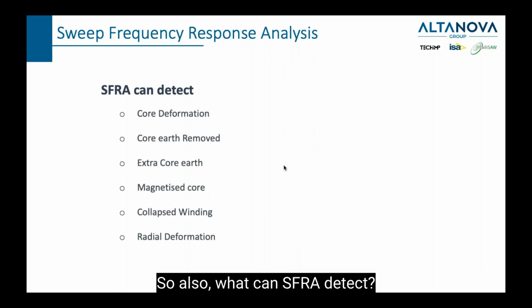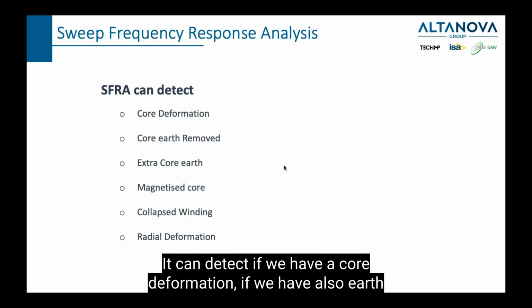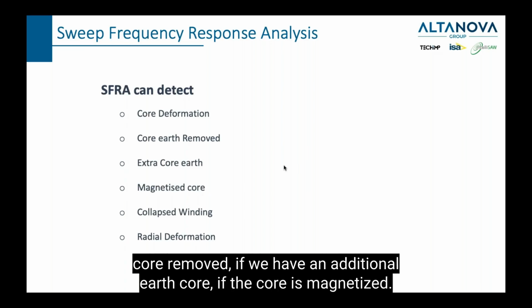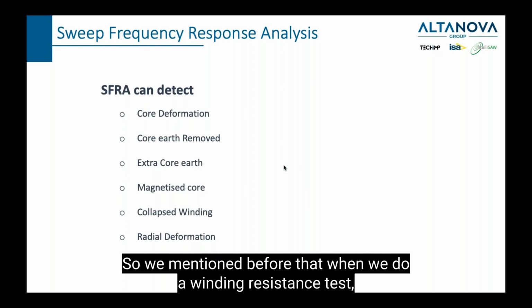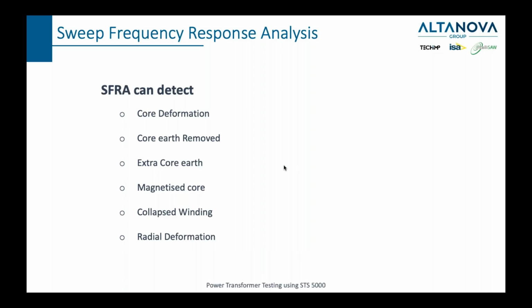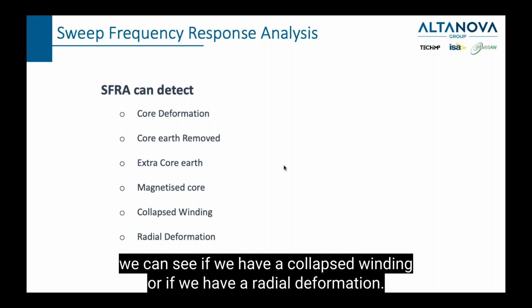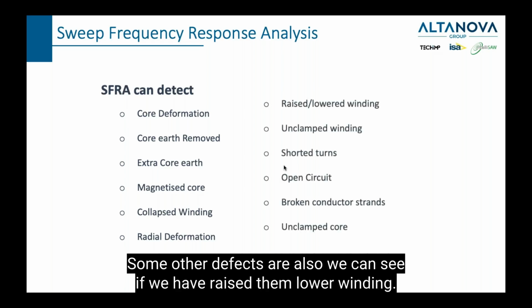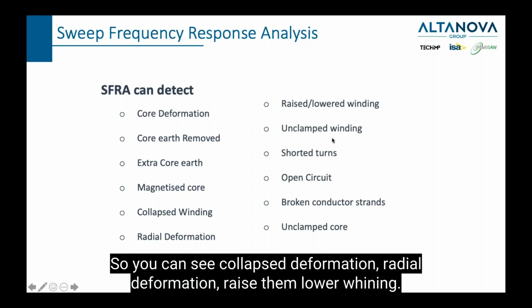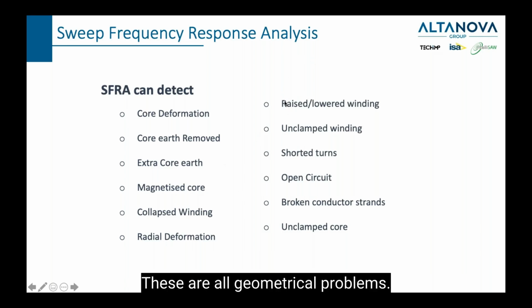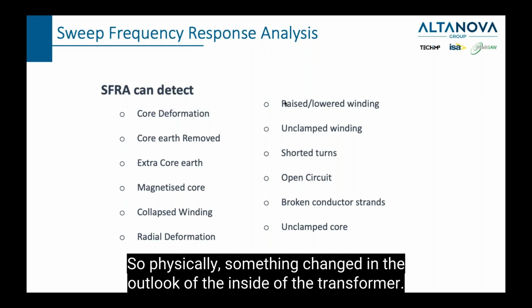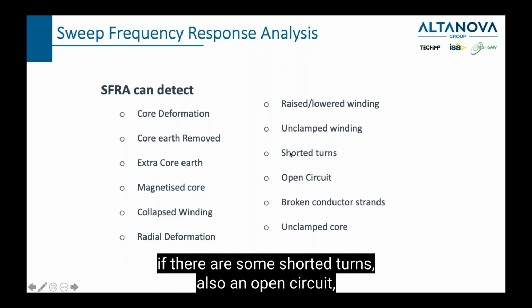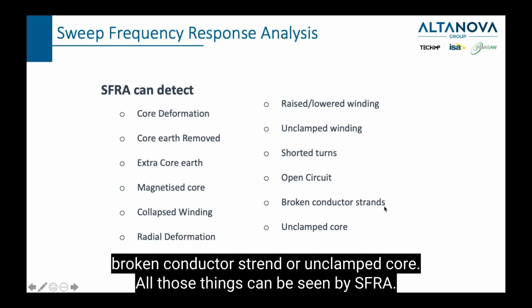So also, what can an SFRA detect? It can detect if we have a core deformation, if we have an earth core removed, if we have an additional earth core, if the core is magnetized. So we mentioned before that when we do a winding resistance test, the core is magnetized and we need to demagnetize it in order to be able to use the transformer again or to test for SFRA. We can see if we have a collapsed winding or if we have a radial deformation. Some other defects: we can see if we have a raised and lowered winding. So you can see collapse deformation, radial deformation, raised and lowered winding. These are all geometrical problems. So physically something changed in the inside of the transformer. We can see if we have some unclamped winding, if there are some shorted turns, also an open circuit, broken conductor strand, or unclamped core. All these things can be seen by SFRA.